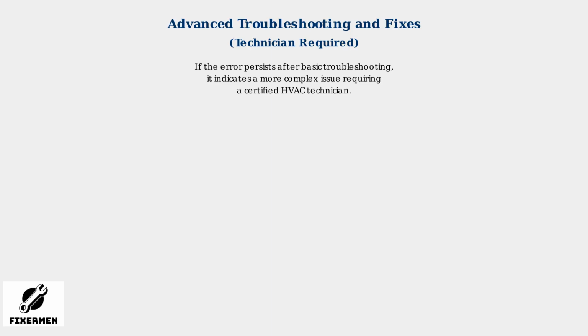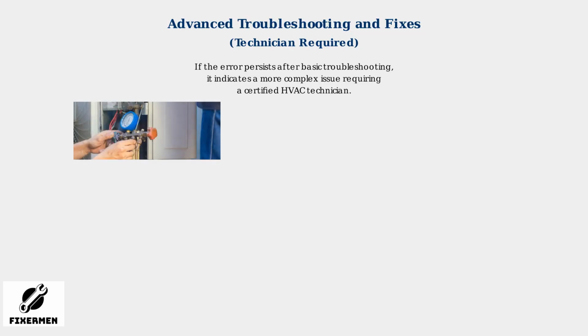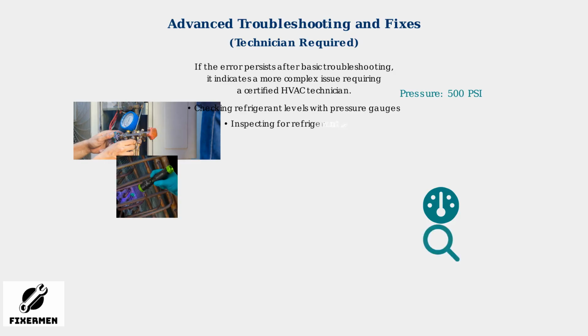When basic troubleshooting fails to resolve error code 45, the issue requires professional intervention from a certified HVAC technician. These complex problems often involve specialized equipment and knowledge beyond typical DIY capabilities. Advanced fixes include checking refrigerant levels using pressure gauges, which measure the system's pressure readings to ensure proper operation. Inspecting for refrigerant leaks using specialized tools like UV lights to detect any escaping refrigerant, or replacing a faulty high-pressure switch that may have failed to function properly.